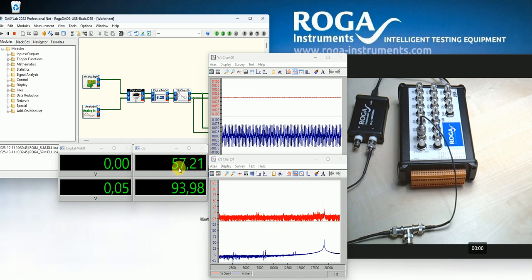high damping. But from this DAQ card we can still see full energy, close to 94 dB, and we see a kind of shadow or illusion frequency. This is the aliasing effect. It is a kind of digital illusion or a digital mirage.